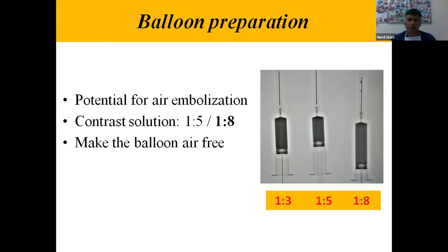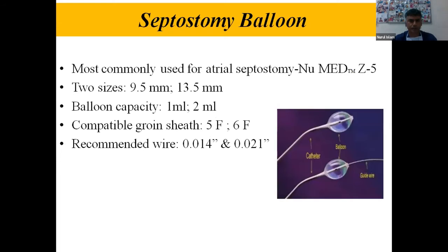You can see that there is not much difference in visibility between these three syringes, but 1:3 dilution can really cause rapid inflation and deflation. So it is a very important part during use of the balloon or inflation.